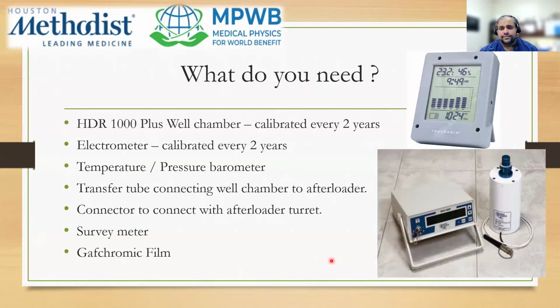So what do you need when doing a source exchange? You need a well chamber that is calibrated every 2 years. You need an electrometer that is also calibrated every 2 years, a temperature and pressure barometer, a transfer tube connecting the well chamber to the afterloader, a connector to connect with the afterloader turret, a survey meter, and GafChromic film.